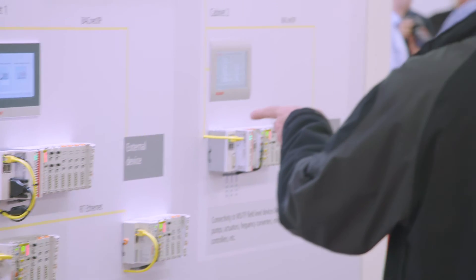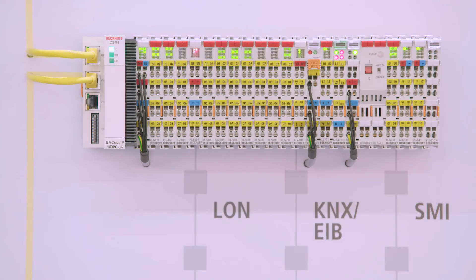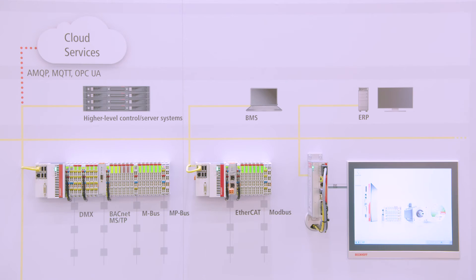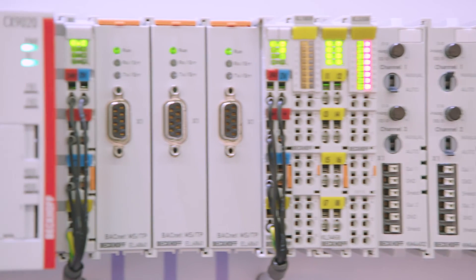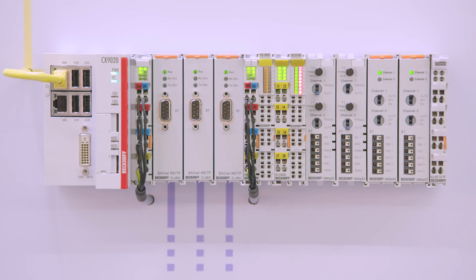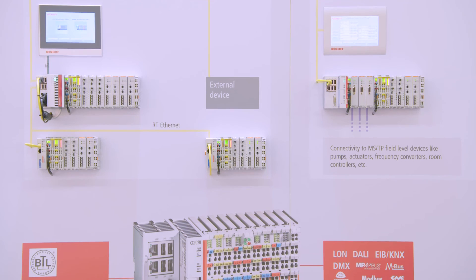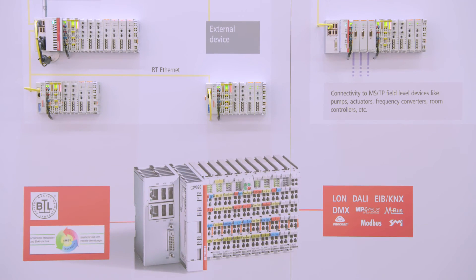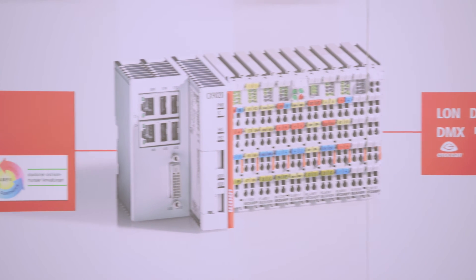New interfaces further expand the range of applications for Beckhoff Building Automation. As well as BACnet IP, Beckhoff now also supports BACnet MSTP with the new EL6861 terminal. The serial interface can be used to directly control and monitor BACnet-compatible field devices such as e.g. pumps, drives and frequency converters, addressing them as sub-bus systems without the need for additional gateways or routers.